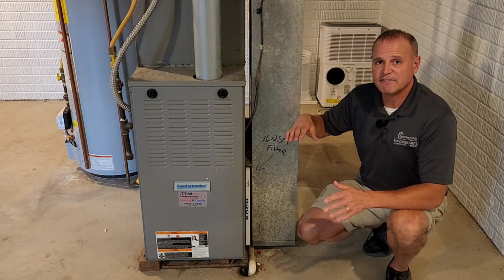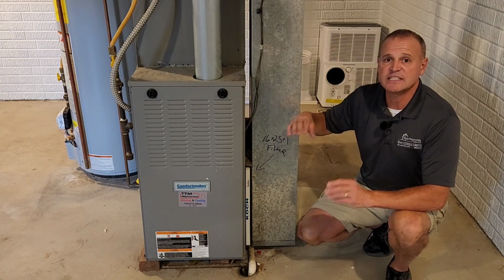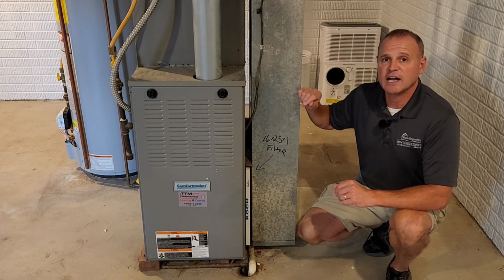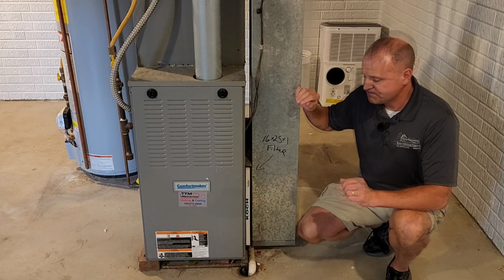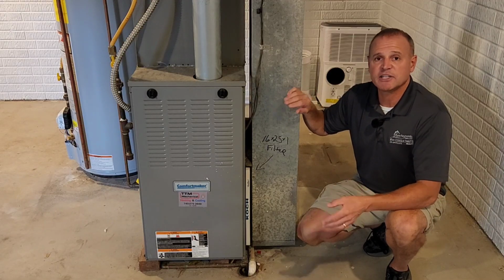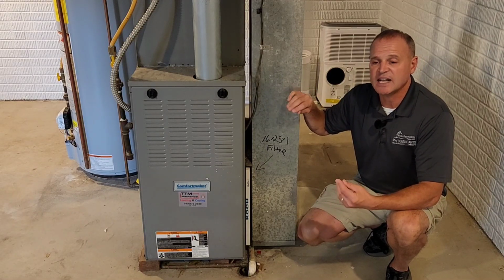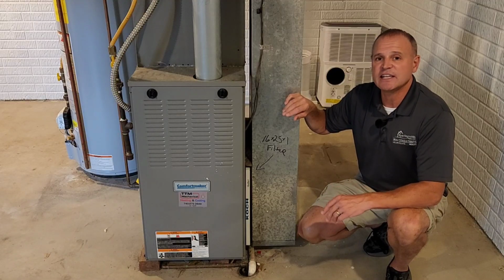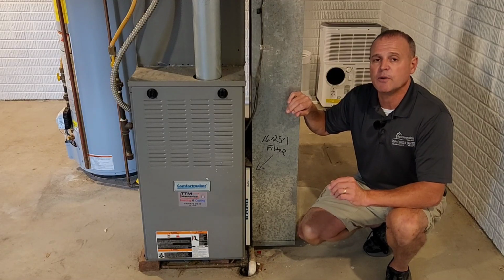So if you want to save thousands of dollars, the best thing you can do is to take care of your furnace by checking on your condensate maybe once a month. When I say checking on, I mean really just checking to make sure that it's open and flowing, and if it's not, or even if it is, it's a good idea to clean that line out just to make sure that it continues to be open and flowing.